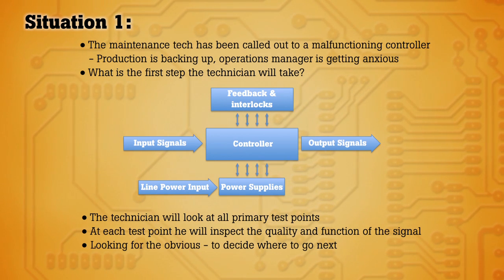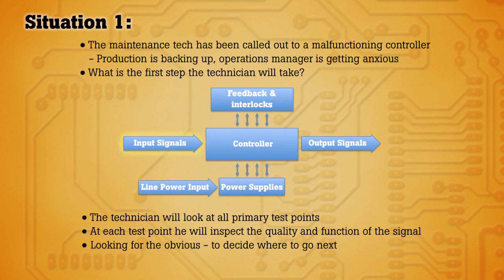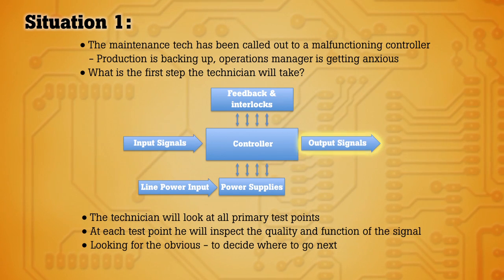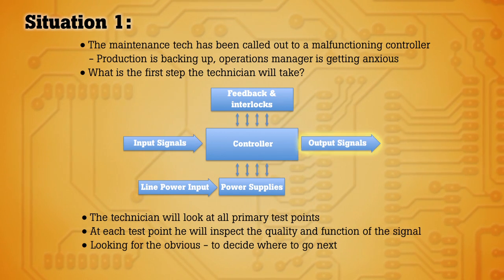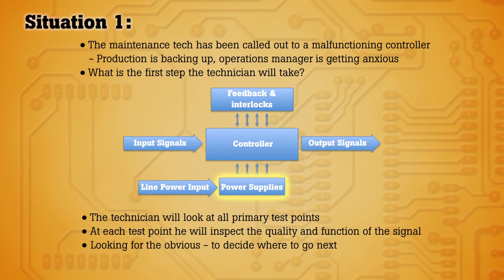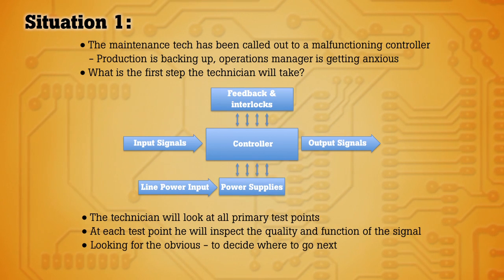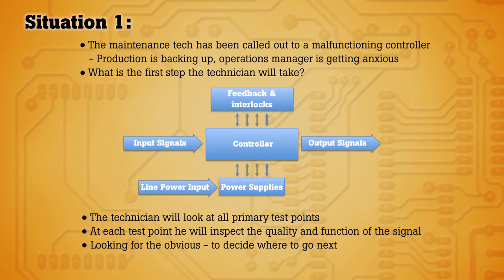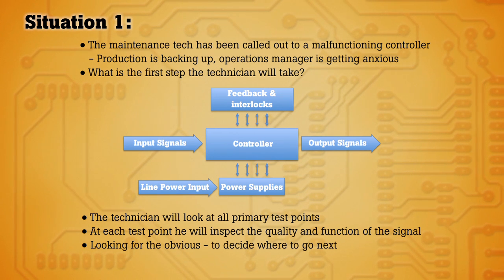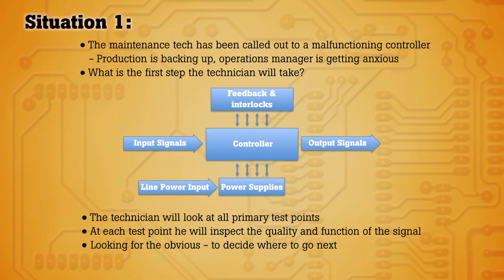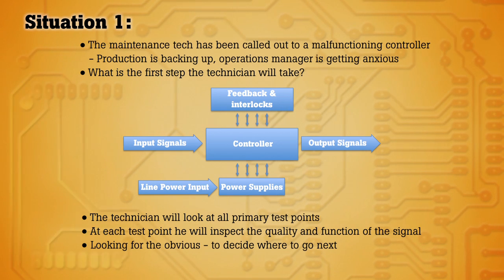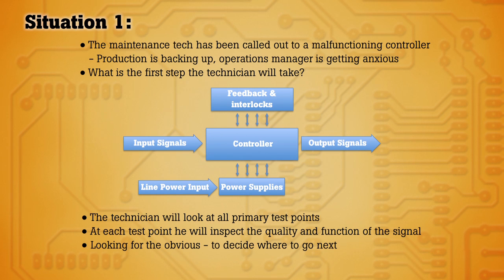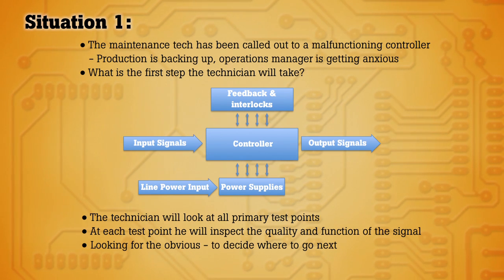Typically you're looking at the input signal, the output control signals, the power supplies, and any feedback or interlock signals that might be causing the malfunction. You'll be checking for any missing signals and looking at the quality of the signals, checking for anything obvious that could point you to a problem on any part of the circuit.